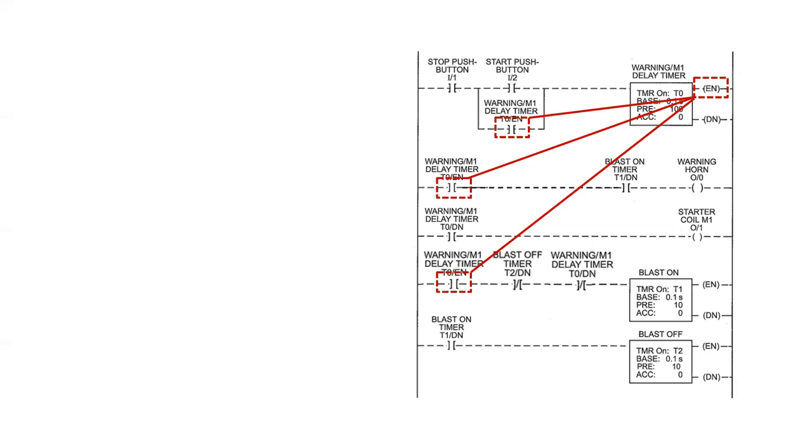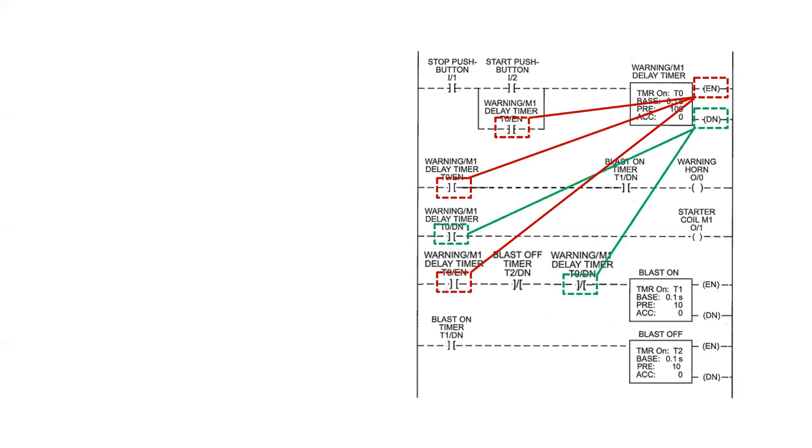For instance, on the warning M1 delay timer, the enabled coil or EN is controlling three separate internal bits at various locations within the PLC program. When the EN coil goes on, all of these inputs will go true. The DN coil is going to be controlling two separate internal bits. One is an examine if off, located down here. The other is an examine if on, located up here.